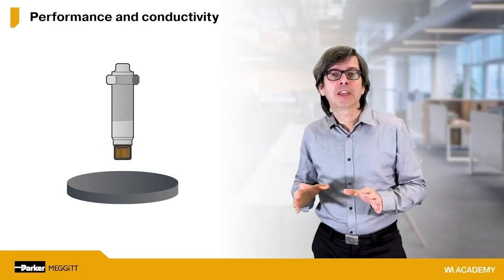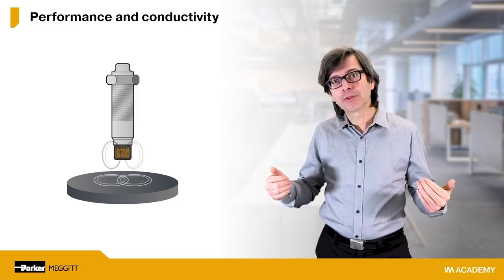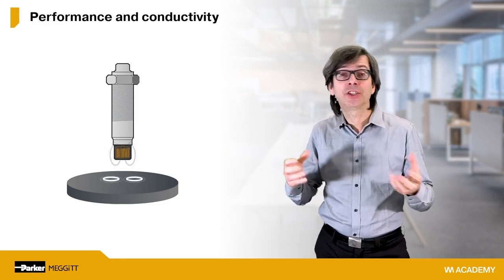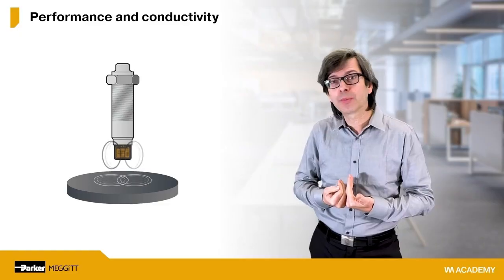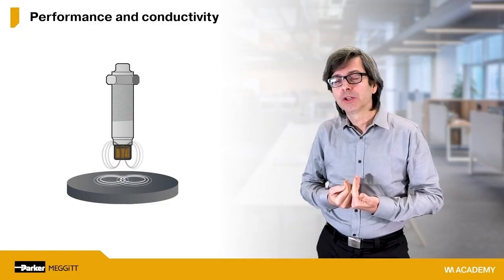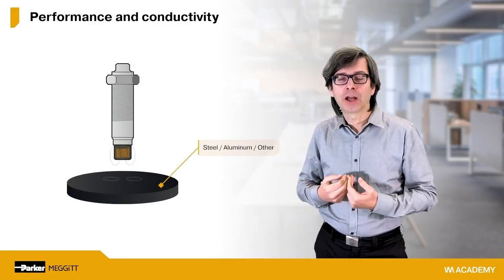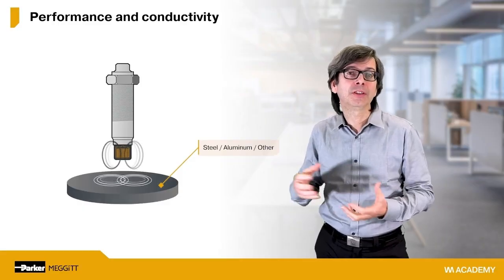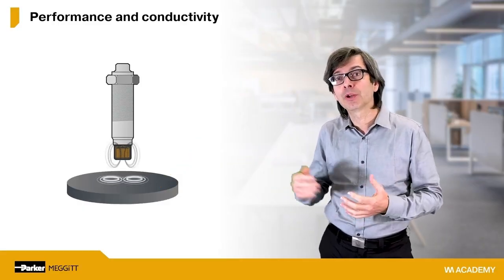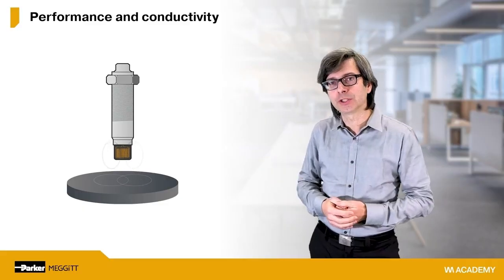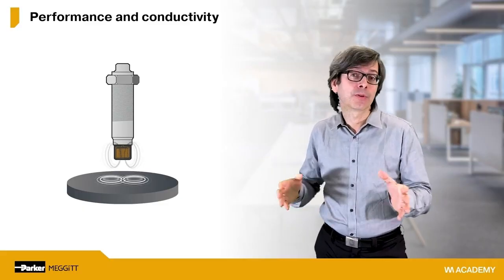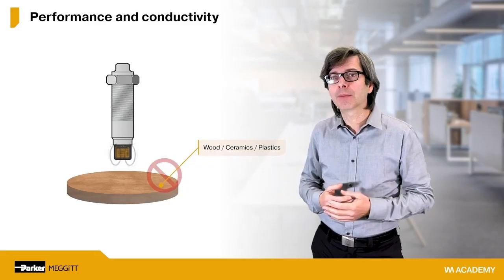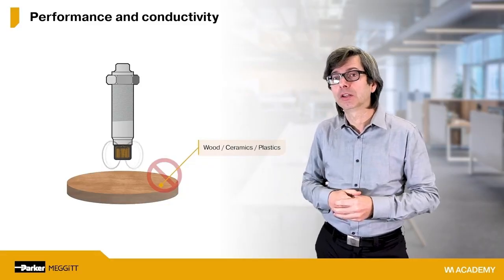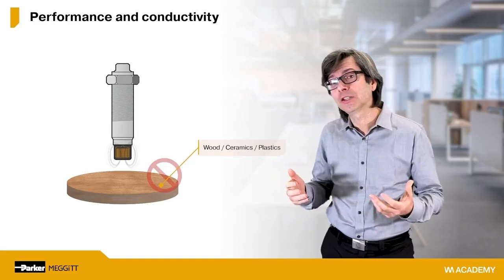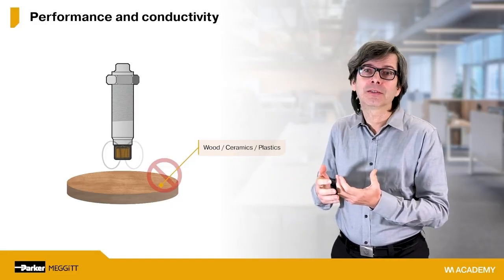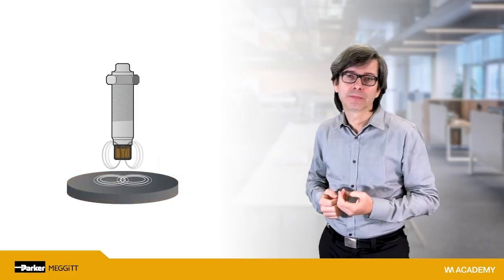It's important to take into account that the performance of the system will change depending on the conductivity properties of the target material. So steel or aluminum or other alloys have different conductivity properties that will produce a different response of the system. For example, if we talk about wood or plastic or ceramic, since they don't conduct electricity, they will not be seen by the sensor.